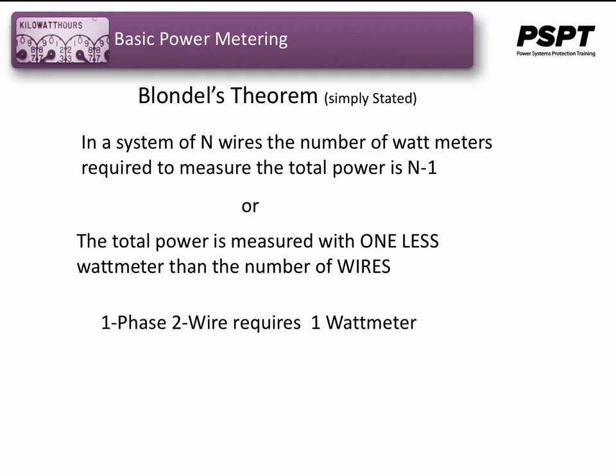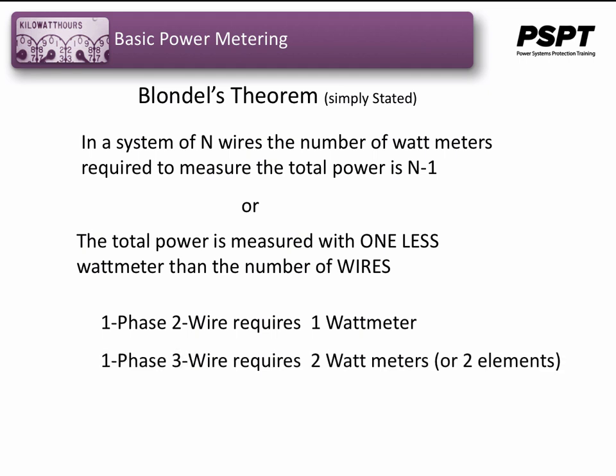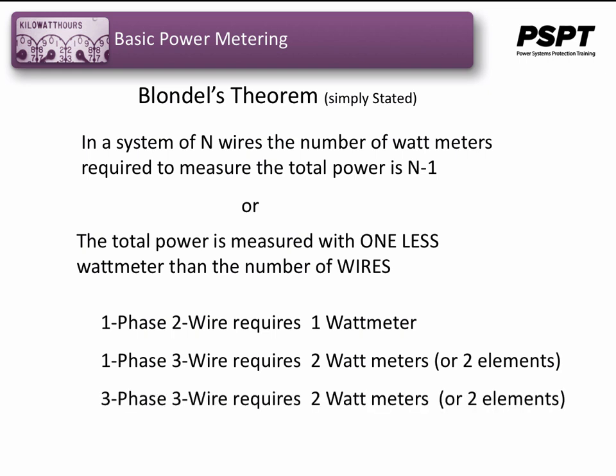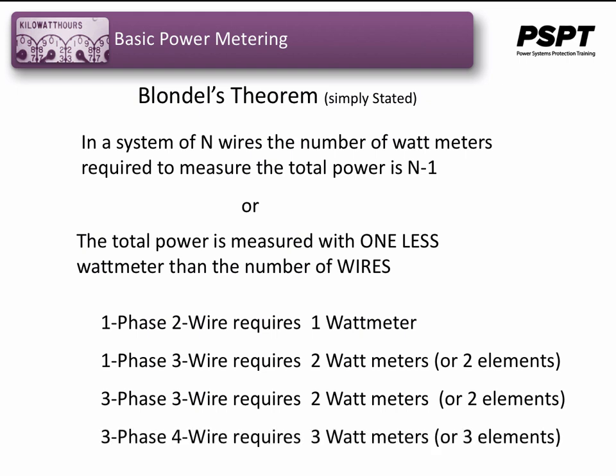A single-phase 2-wire system requires 1 wattmeter. A single-phase 3-wire system requires 2 wattmeters, or 2 elements. A 3-phase 3-wire system requires 2 wattmeters, or 2 elements. And a 3-phase 4-wire system requires 3 wattmeters, or a wattmeter with 3 elements.